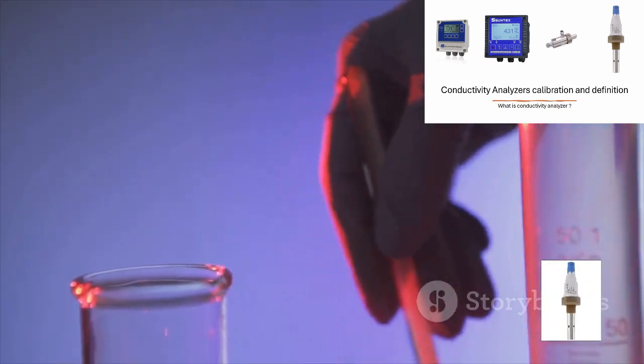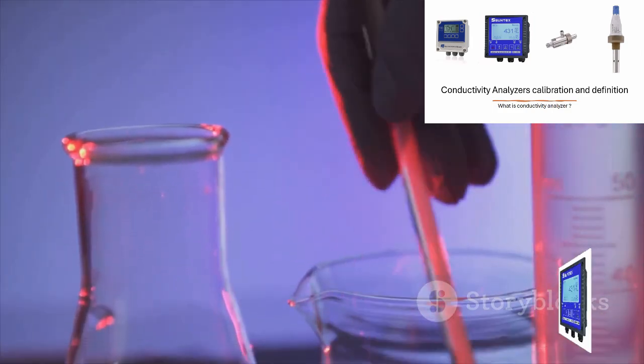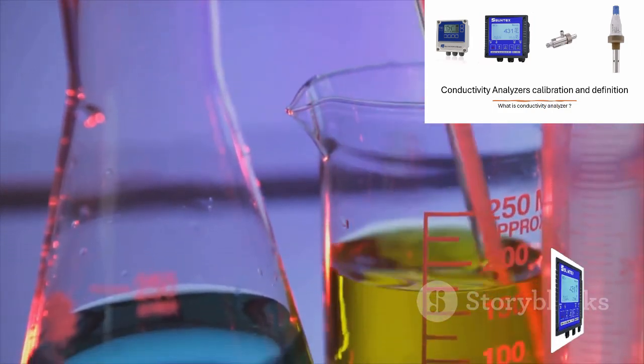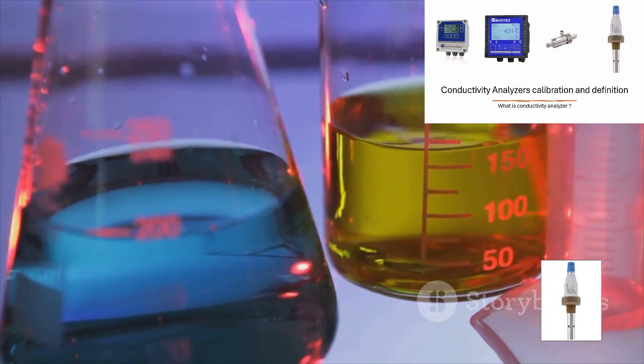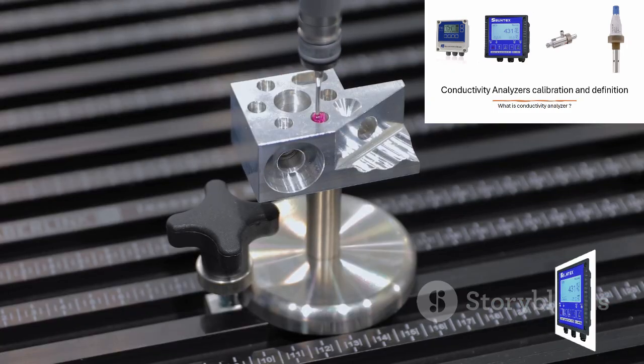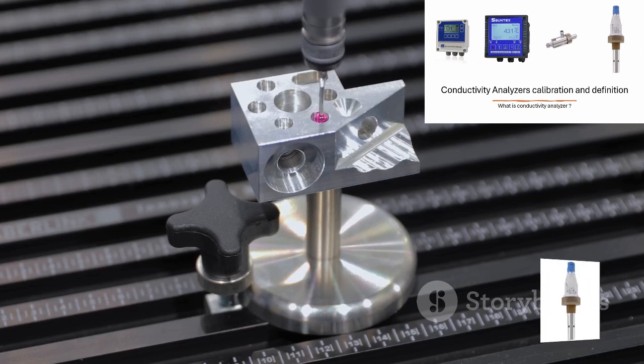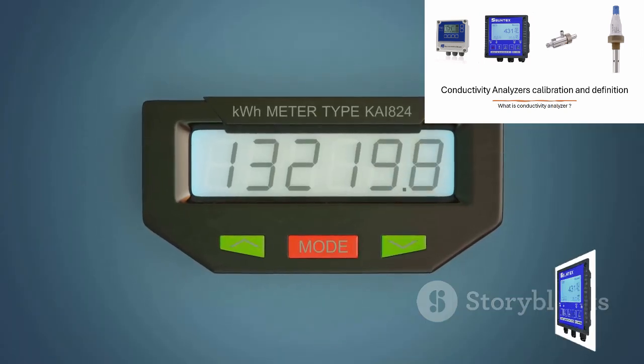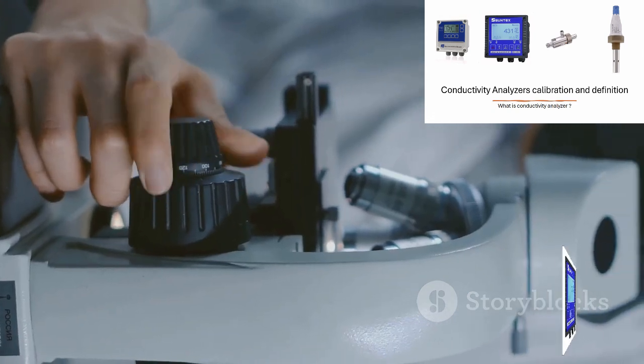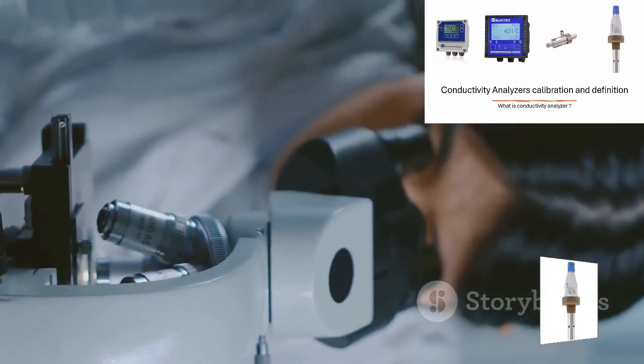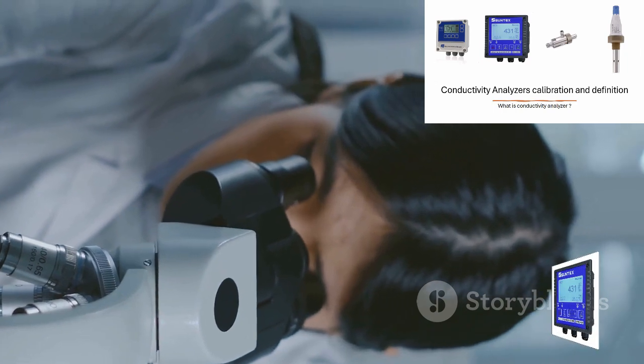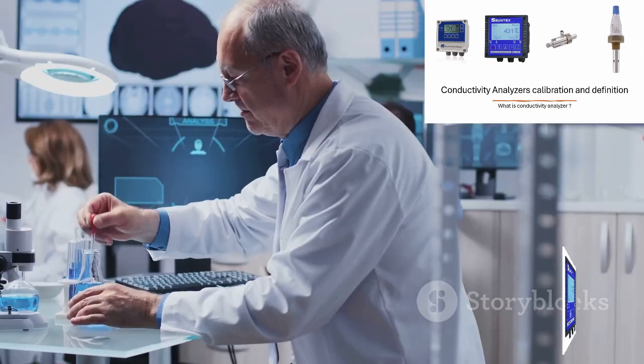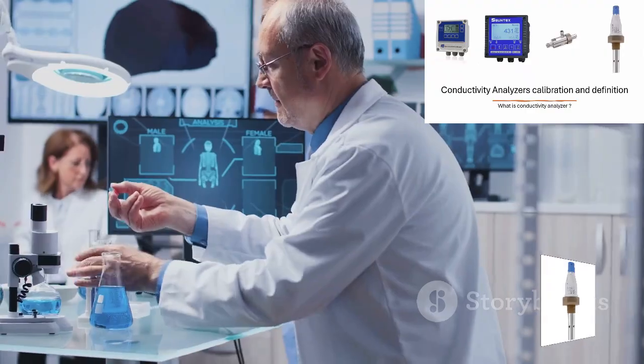Finally, while the standard solution method is the most common, it's cool to know there's another way called the cell constant method. The cell constant is a unique value for each specific probe that relates to its physical design. In this method, you don't adjust the meter's reading. Instead, you measure a standard solution and use the result to calculate and update the sensor's cell constant within the meter's settings.